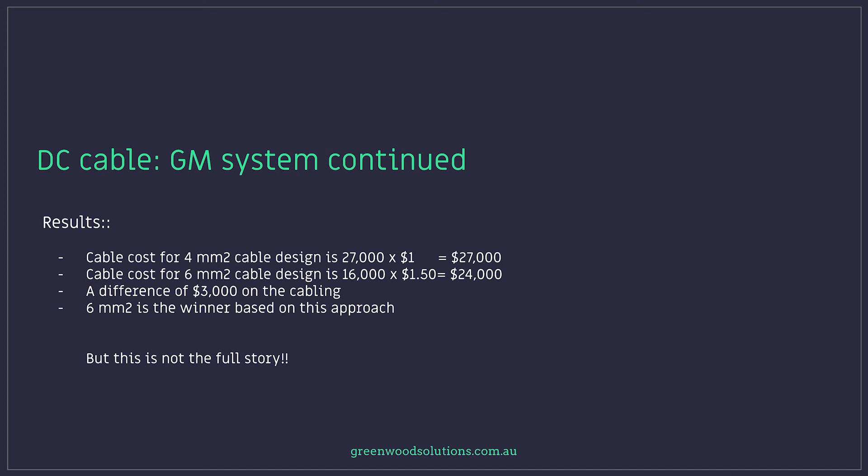So that's a difference of $3,000 just on the cabling. 6mm squared is the winner based on this approach. But this is not the full story.